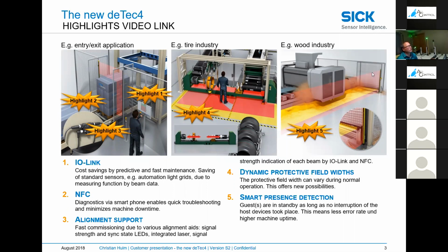You see you have a vertical light curtain and a horizontal light curtain. What happens is it's a master slave or a host guest configuration. The guest is asleep. This yellow one goes to sleep and wakes up when somebody infringes the host. That's the basic concept. So that allows for the guest to not get false trips. So it's one of the neat applications or neat features built right into these light curtains.